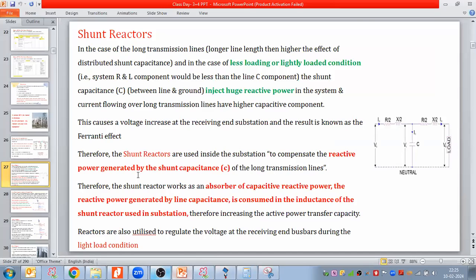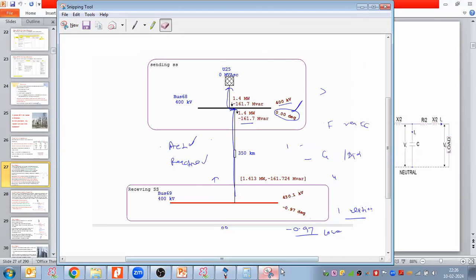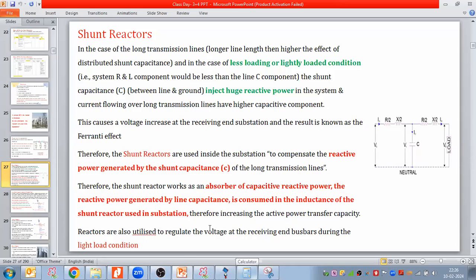So now coming to here, shunt reactors are used in the substations to compensate the reactive power generated by the shunt capacitance of the long transmission line. And shunt reactors work as an absorber of the capacitive reactive power. The reactive power generated by the line capacitance is consumed by the inductance of the shunt reactors used in the substations. Therefore, while increasing the active power transfer capacity, reactors are utilized to regulate the voltage. You can see in this, earlier it was 430 kV, now it is 400 kV. So it regulates the voltage at the receiving end bus bar during the light load conditions.